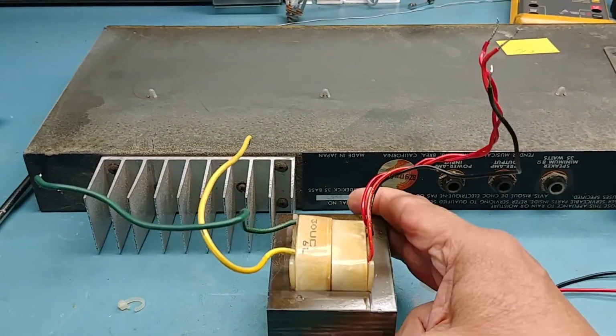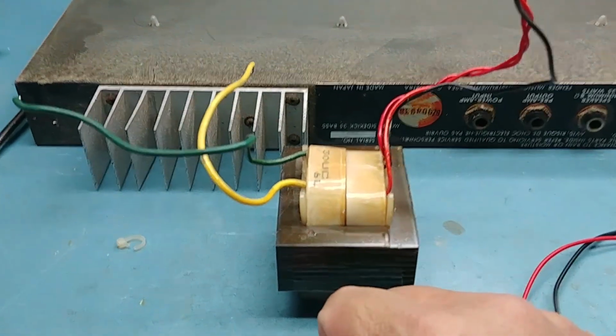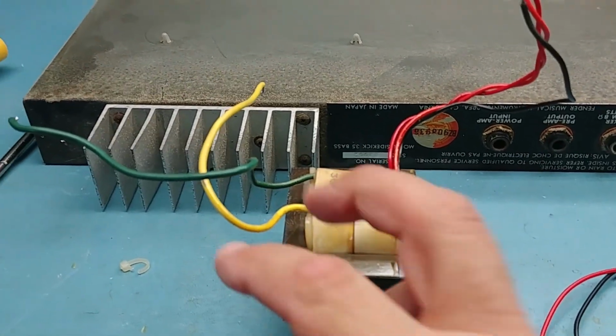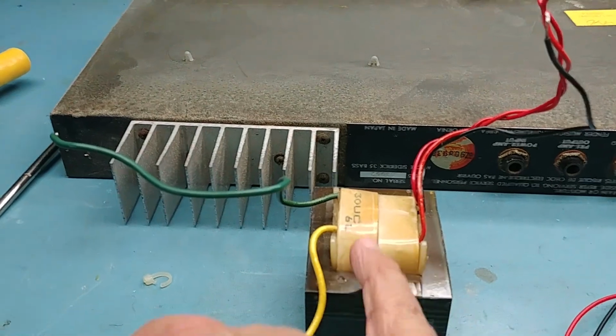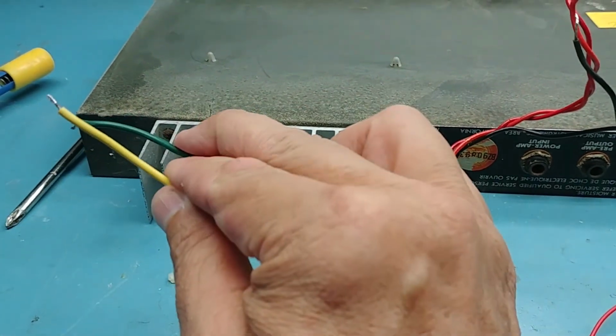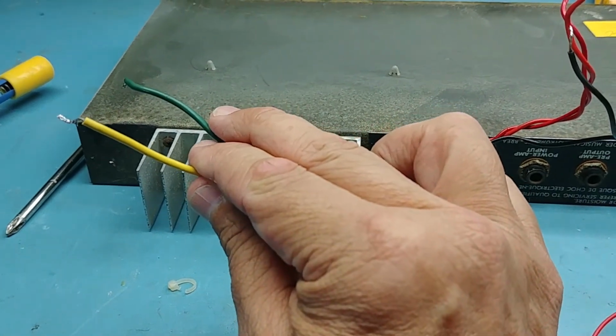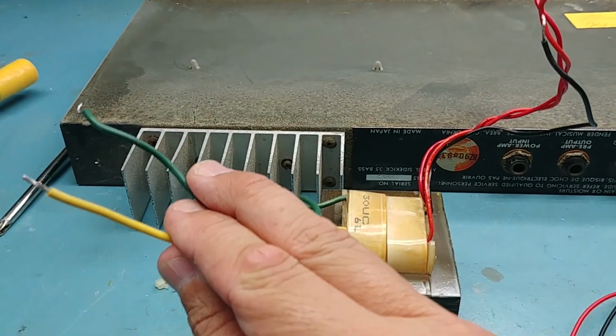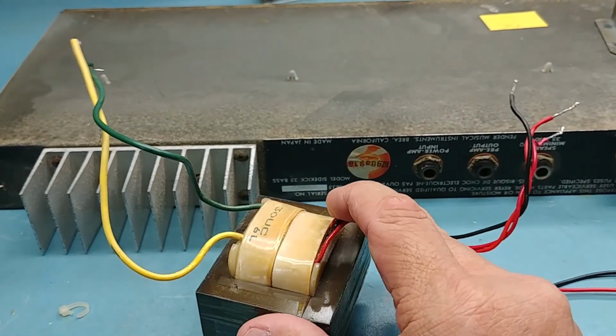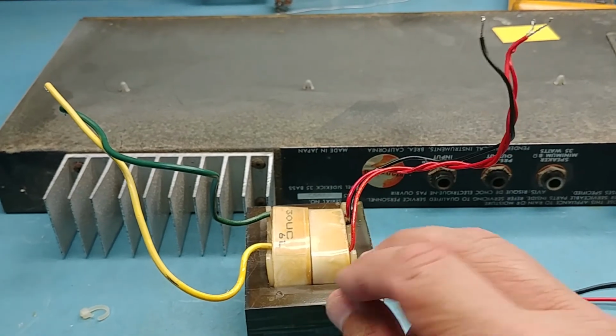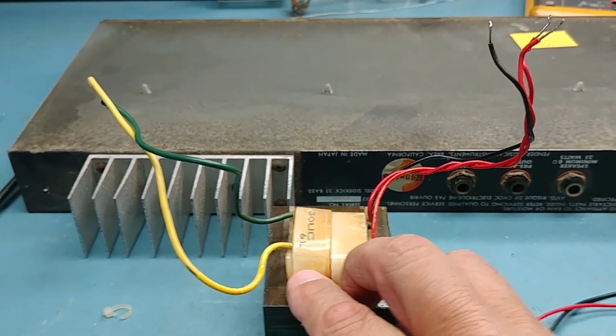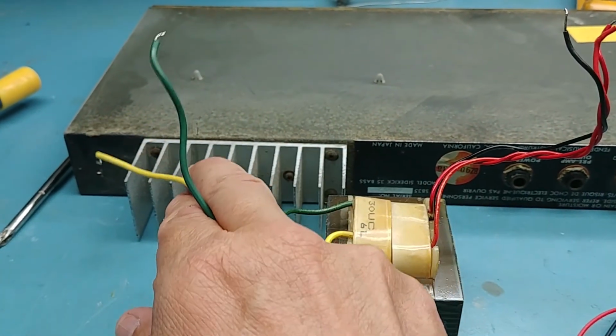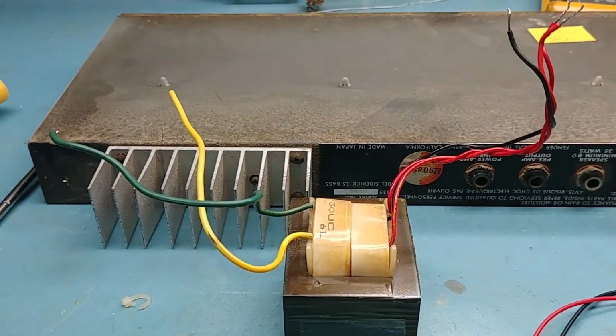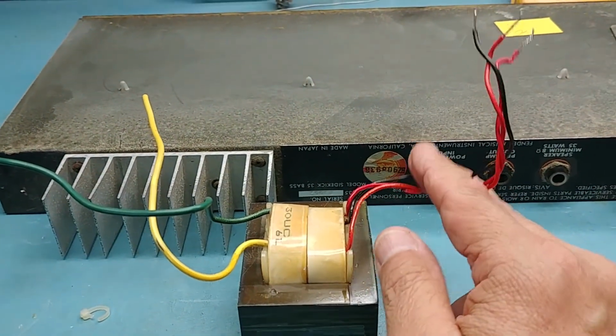So when I say winding, transformer windings, it's basically a big coil of wire. So physically inside of this transformer, these two wires are connected to each other. It's one big long string of wire put in a coil, and the same with the secondary winding. But the two windings don't touch each other. So if you put an AC voltage here, it gets induced onto this secondary winding.